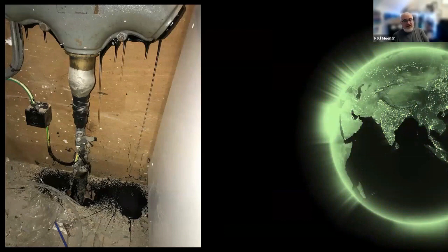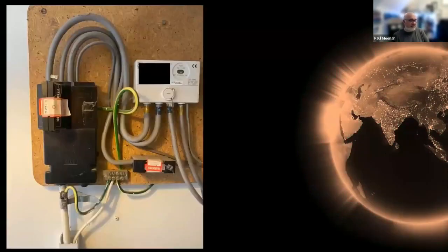And in England, we have old networks. You think our networks are near 100 years old. So we have metal cutouts, pitch resin filled, which can leak when they get hot because of loading. And that's just an image of an earthing system that connects to the sheath of the cable. It's an old lead, bitumen impregnated sheath cable. These are more modern in England. We have a supply cable that comes into a service fuse, and in a lot of places the earthing will connect either to the sheath of the cable or actually connect to the neutral, and they're TN-S, TN-C-S systems.